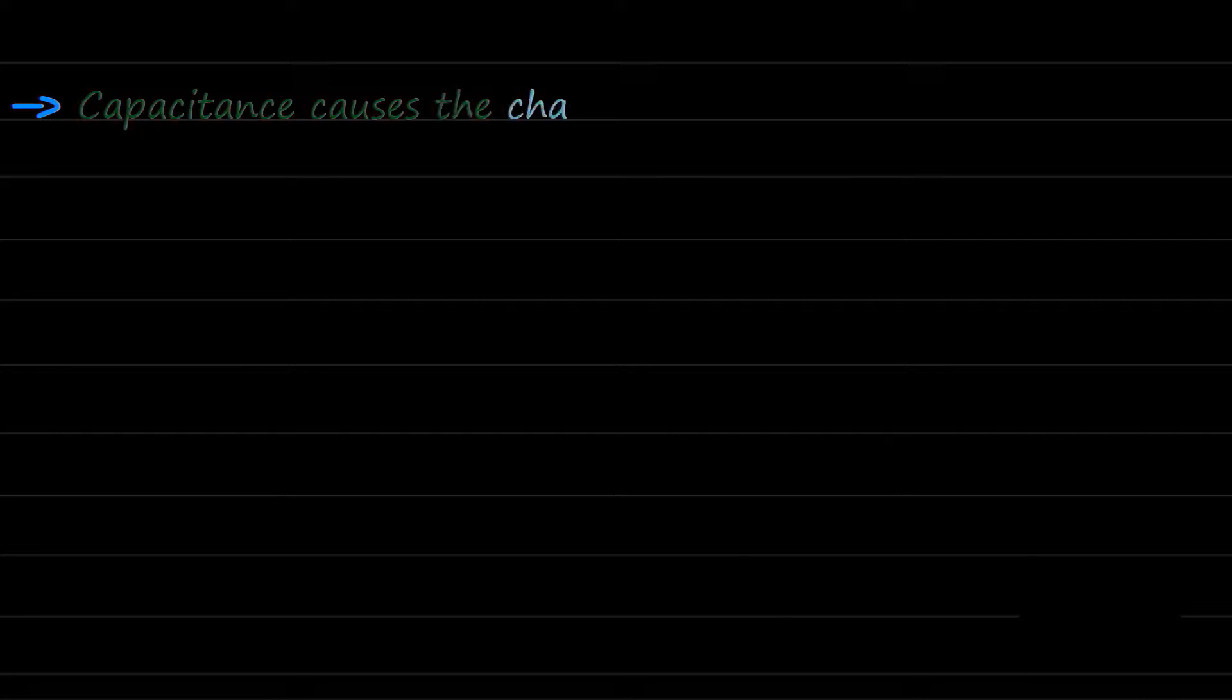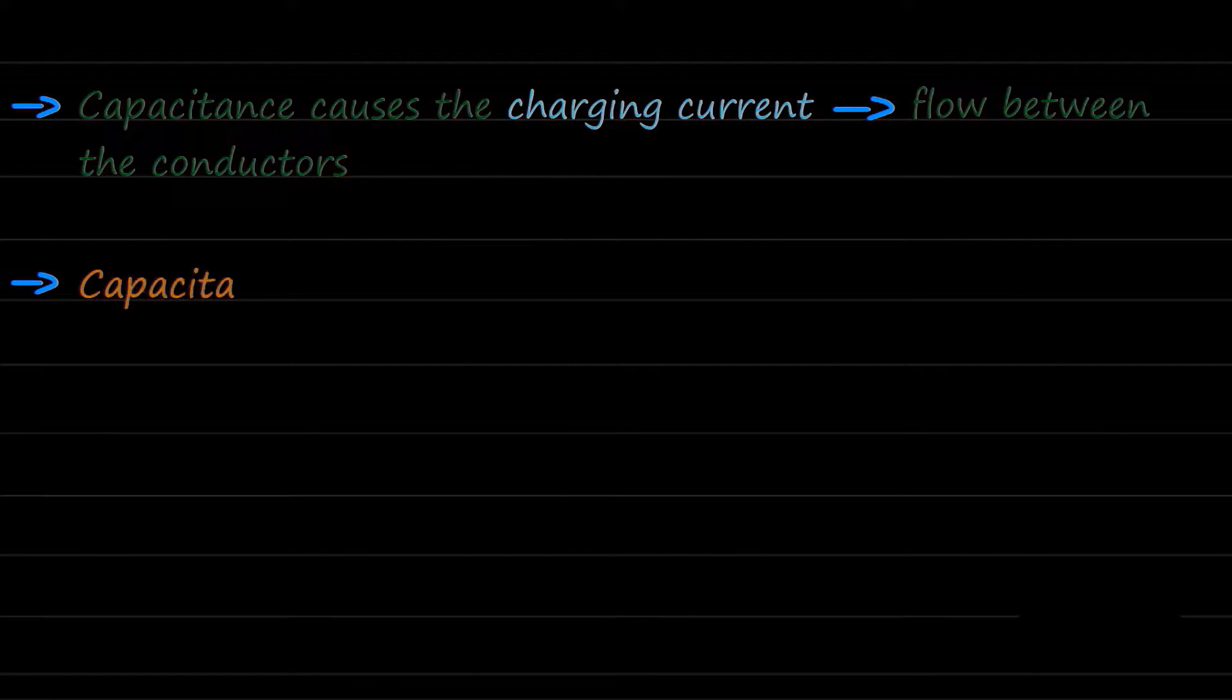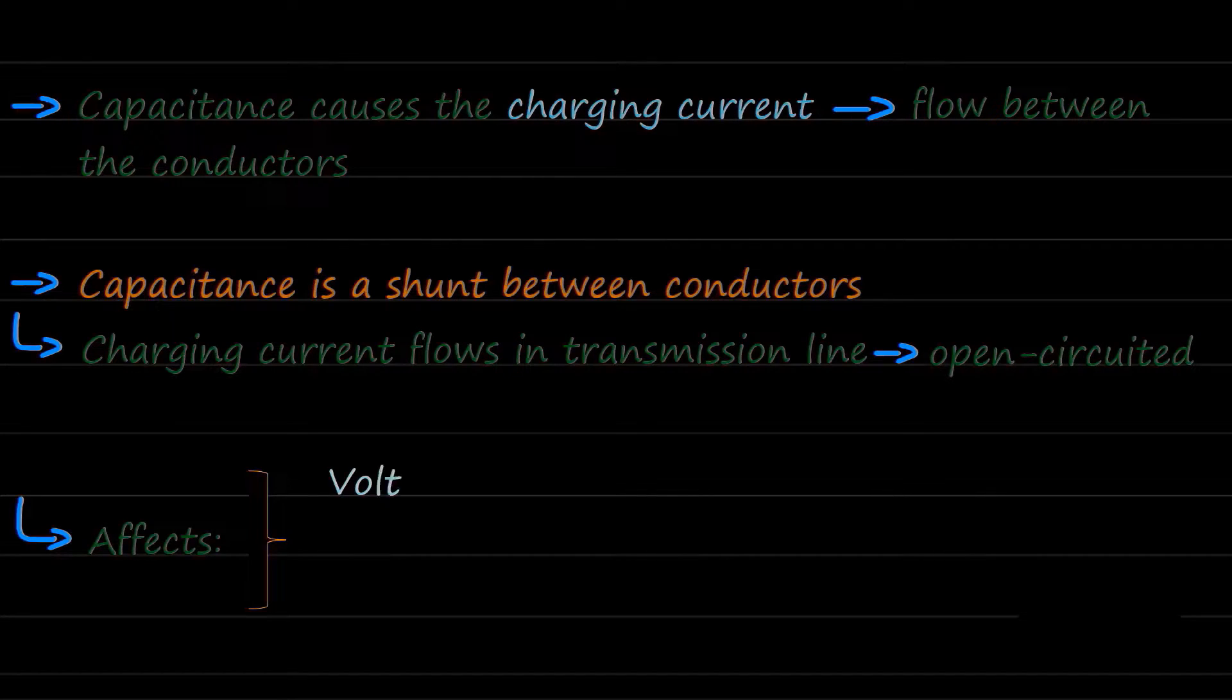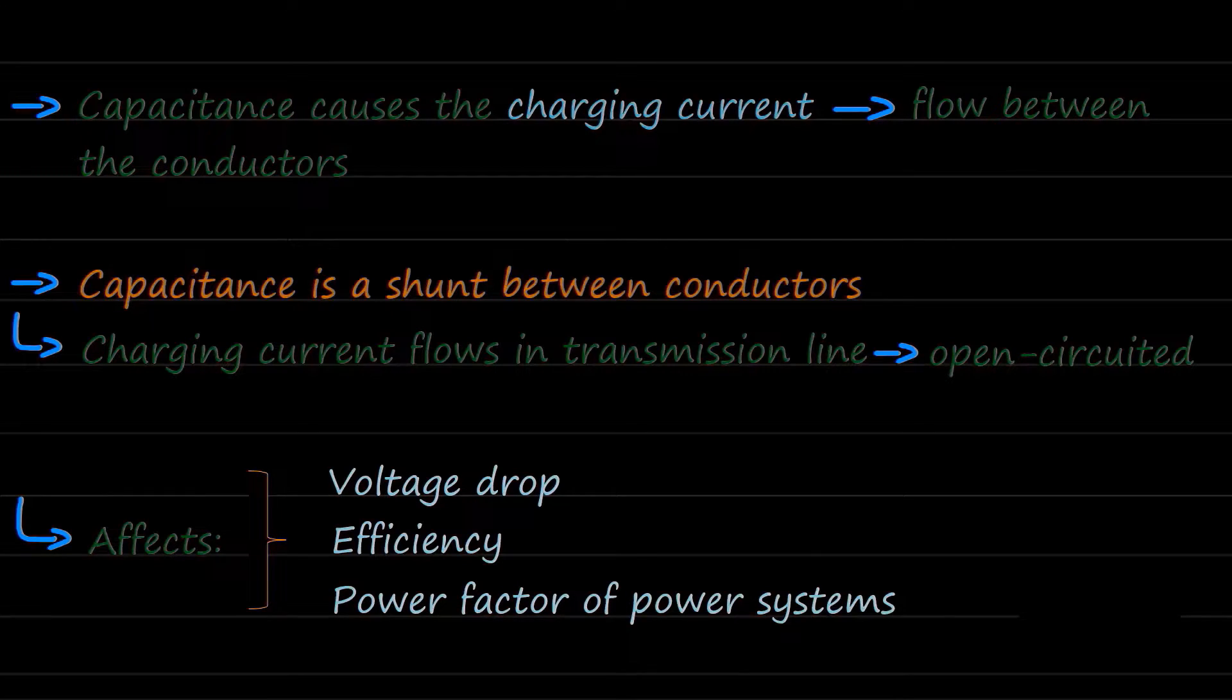Capacitance causes the charging current to flow between the conductors. And since capacitance is a shunt between conductors, charging current flows in a transmission line even when it is open circuited. Therefore, it affects the voltage drop, efficiency, and power factor of the power systems.